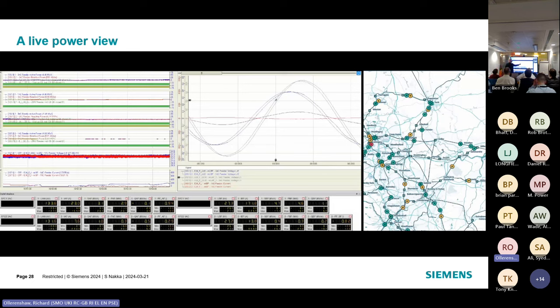And here you see a bit of train load, and you can see the dirty waveform that trains create. The difference you would normally see in a railway traction power supply is that you'd see that same shape on the grid voltage as well. You see it pass directly through. But as you see here, the grid voltage remains pretty much the same.